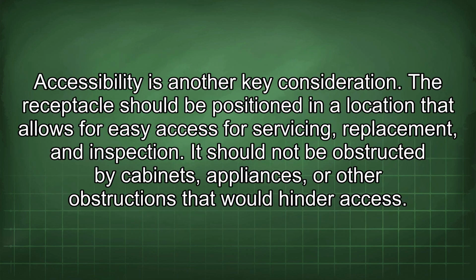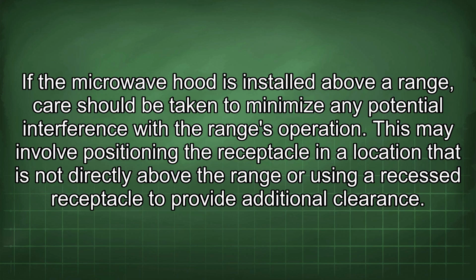Accessibility is another key consideration. The receptacle should be positioned in a location that allows for easy access for servicing, replacement, and inspection. It should not be obstructed by cabinets, appliances, or other obstructions that would hinder access. If the microwave hood is installed above a range, care should be taken to minimize any potential interference with the range's operation. This may involve positioning the receptacle in a location that is not directly above the range or using a recessed receptacle to provide additional clearance.